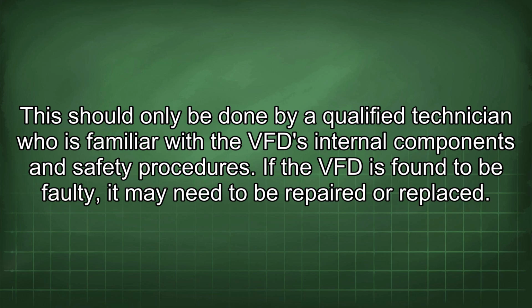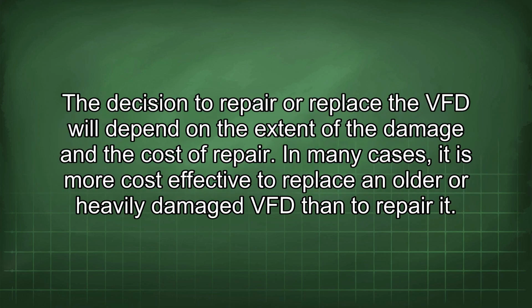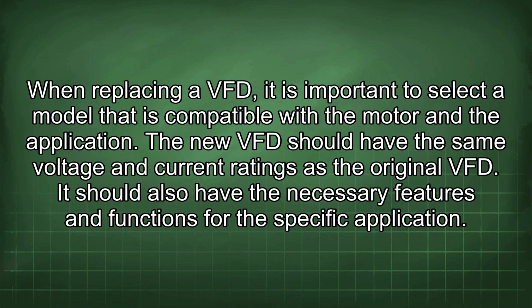If the VFD is found to be faulty, it may need to be repaired or replaced. The decision to repair or replace the VFD will depend on the extent of the damage and the cost of repair. In many cases, it is more cost-effective to replace an old or heavily damaged VFD than to repair it. When replacing a VFD, it is important to select a model that is compatible with the motor and the application. The new VFD should have the same voltage and current ratings as the original VFD. It should also have the necessary features and functions for the specific application.